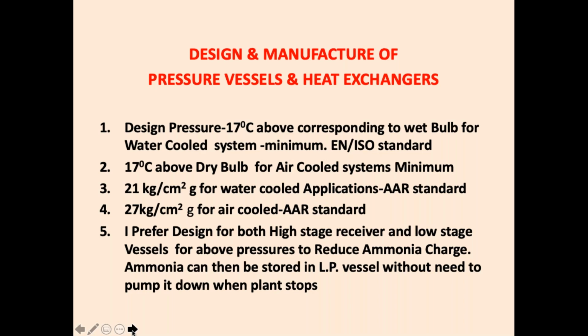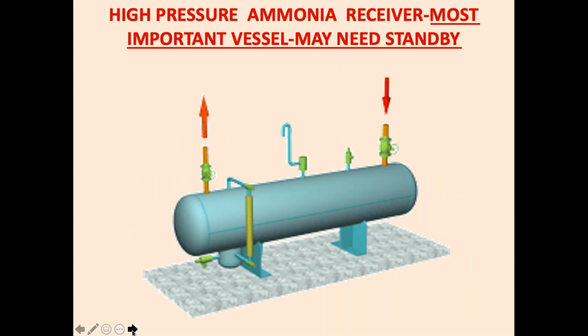Then, a most important point: people design the low side of the system and the high side of the system for different pressures. My suggestion, and what I personally do, is to design both the high side receiver and low side vessels for the same pressures. It doesn't cost more. Instead of 12 thickness plate or 14, you may have to use the next size of 16. But it reduces the sizes of the vessels considerably, because then you don't have to pump down every time you stop the plant or develop a problem in the system. Ammonia can then be stored in the low side LP vessel without pumping it down. So in my plants, I always design that.